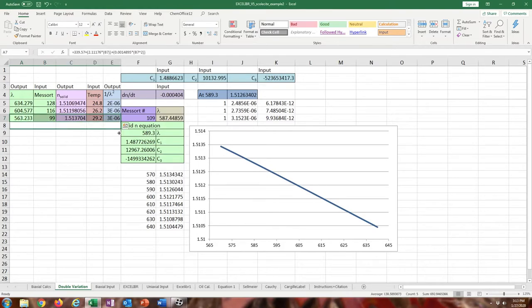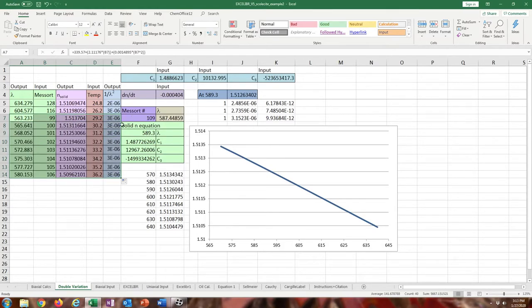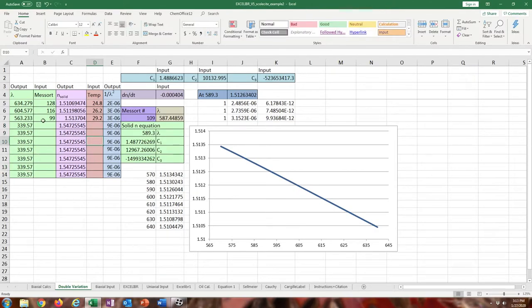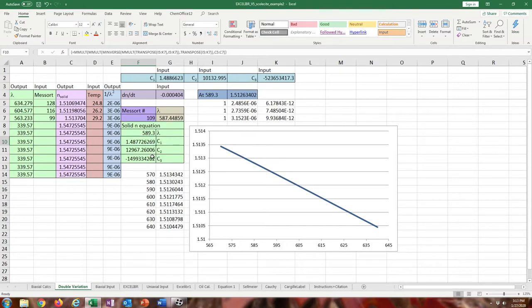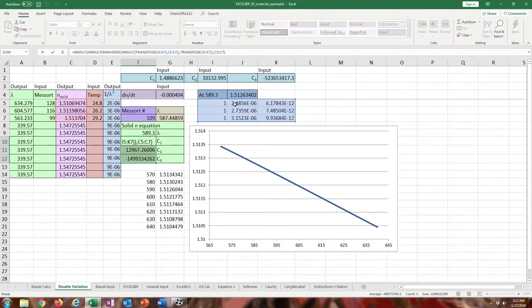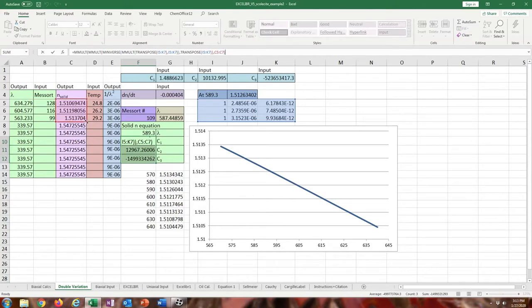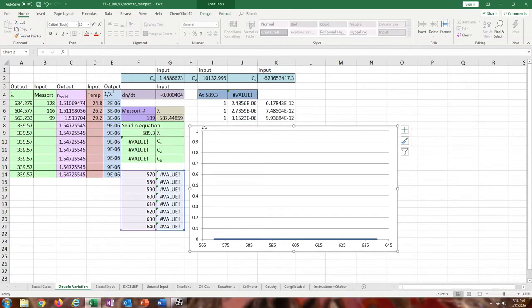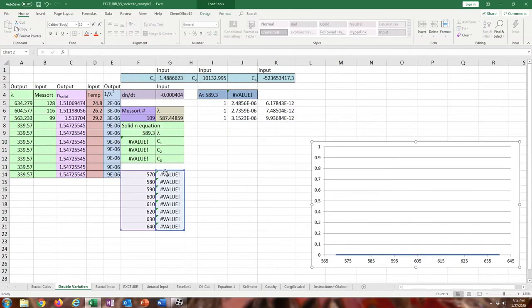Here I'm showing how to expand your matrix. Just the same thing with the oil calibration. You can just drag it down, expand the number of entries, but you have to expand this matrix also, which is referencing the inputs on the left. This calculation is made so that it doesn't have to be a square matrix. You can include as many entries as you want. It'll just perform a least squares fit for it.